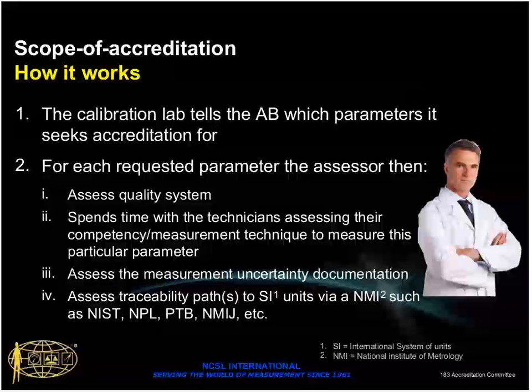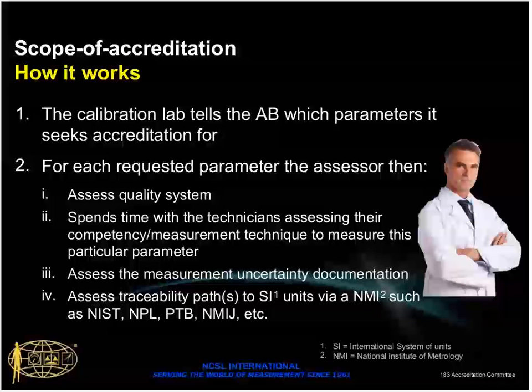Now on the next slide, looking at the certificate of accreditation is only part of the story. So when you go to an accredited lab and you see it's an accredited lab, that's one thing. But you want to see what they're accredited for. This is absolutely vital because some people are accredited for a small amount of parameters. This could be the main functions of a multifunction instrument, say voltage and current, but might not include some of the more complex and relatively obscure measurements which you may well need.